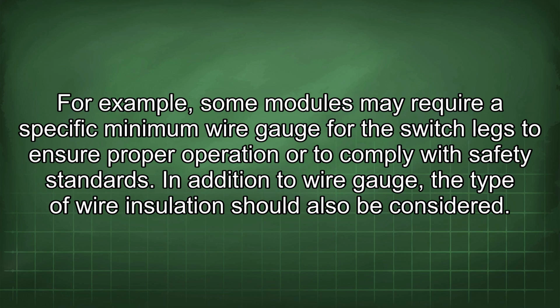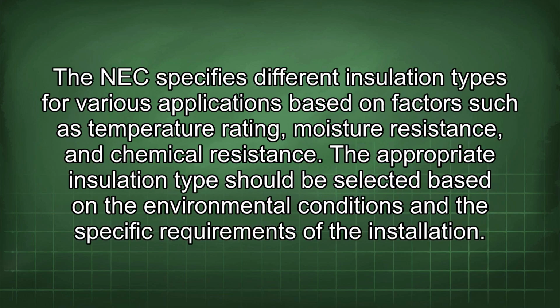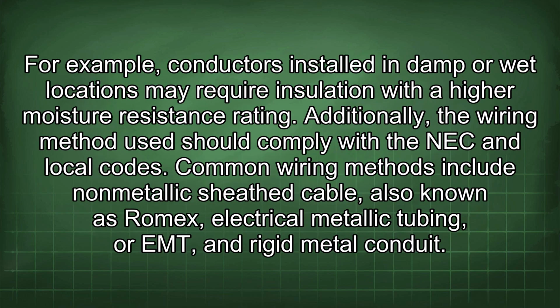In addition to wire gauge, the type of wire insulation should also be considered. The NEC specifies different insulation types for various applications based on factors such as temperature rating, moisture resistance, and chemical resistance. The appropriate insulation type should be selected based on the environmental conditions and the specific requirements of the installation. For example, conductors installed in damp or wet locations may require insulation with a high moisture resistance rating.